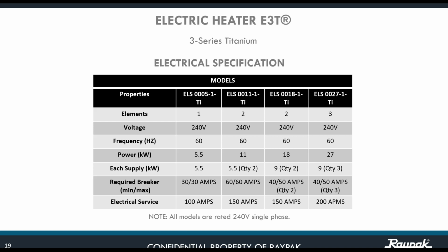Required breaker for the 5.5 is 30 and 30 amps, minimum and maximum. For the 11 it is 60 and 60. For the 18 it is 40 minimum, 50 max. And now we need 2 for the 18, and we're going to see why 2. And for the 27, we have 3 breakers that are required, that can be either 40 amps or 50 amps maximum.